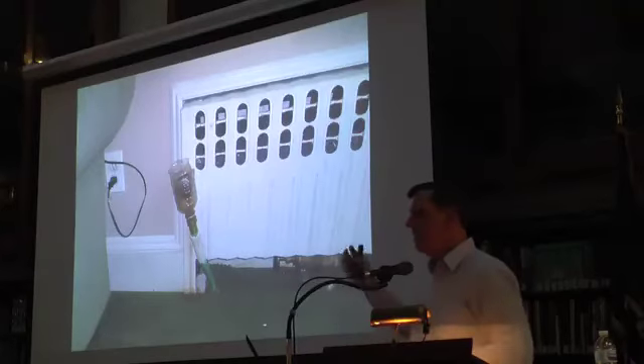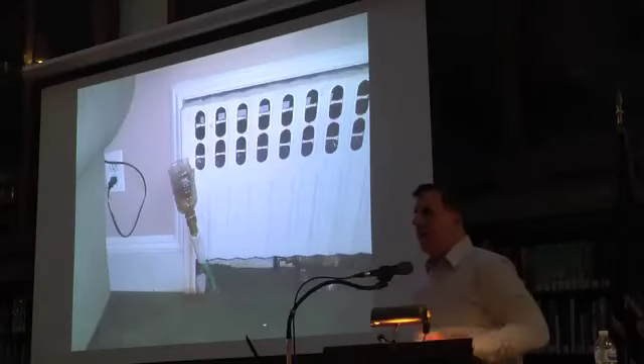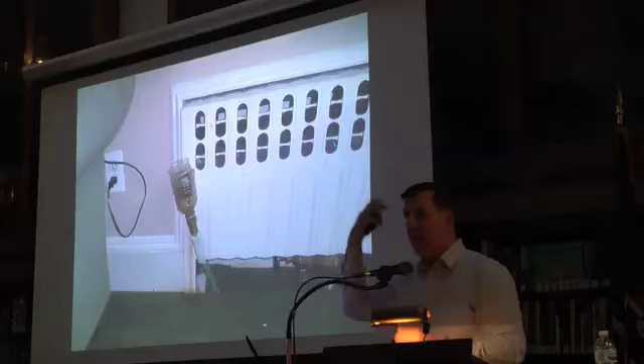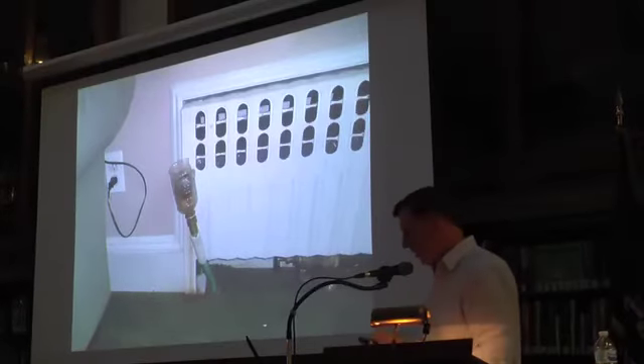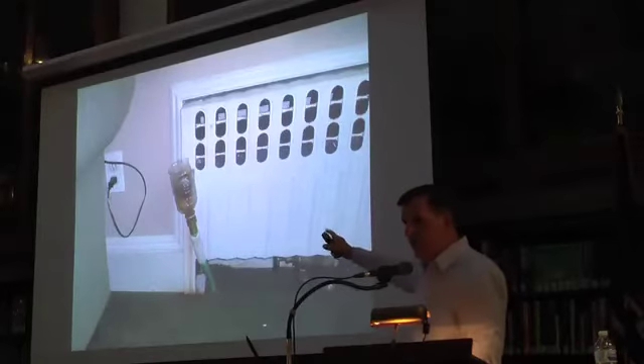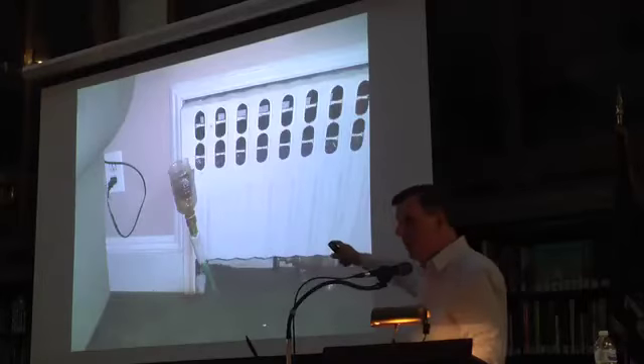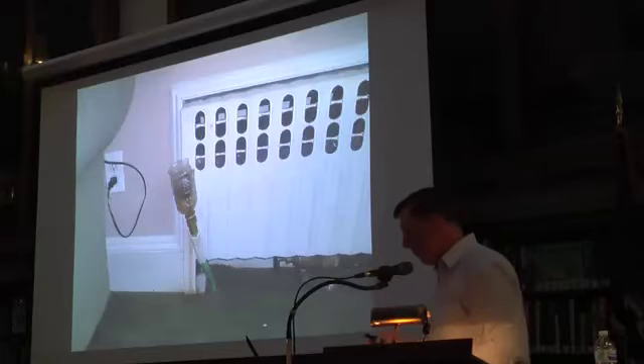And naturally, the steam goes into this cold crawl space and it condenses. There's no insulation on anything, so it condenses, and the water can't drain back against steam that's coming at it with a gale force wind, so the water starts squirting out of the air vent that's on the radiator. So the plumber comes back and he solves it by putting that soda bottle over the air vent. Just cut a hole in the side, put it over the air vent, and then he took the garden hose and stuck it on the bottle and drilled a hole so it would go down into the crawl space.